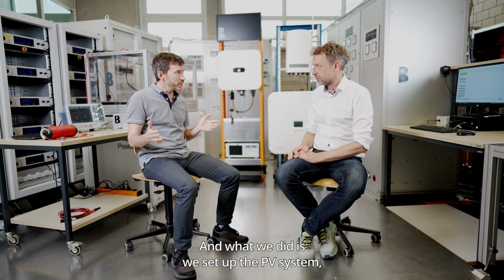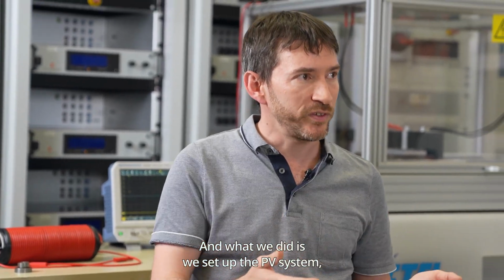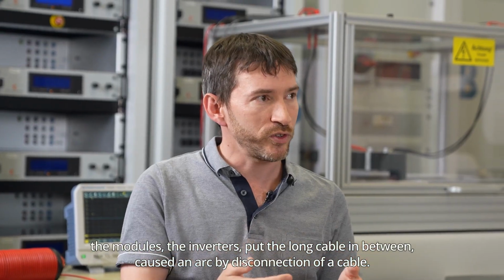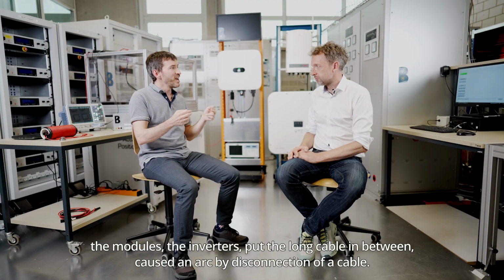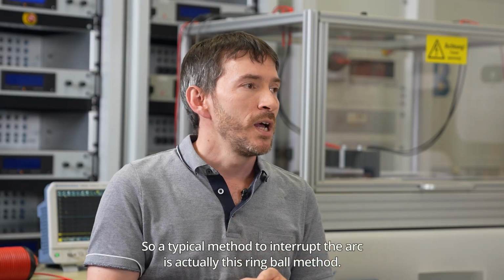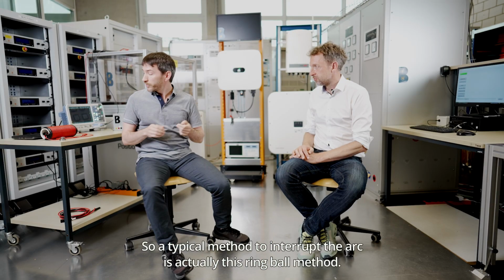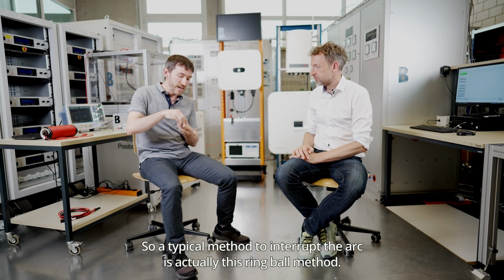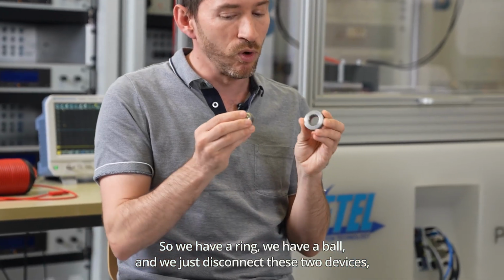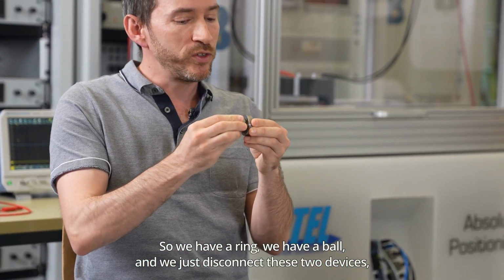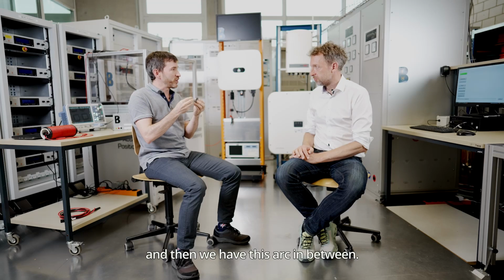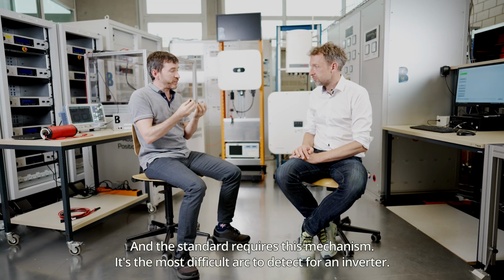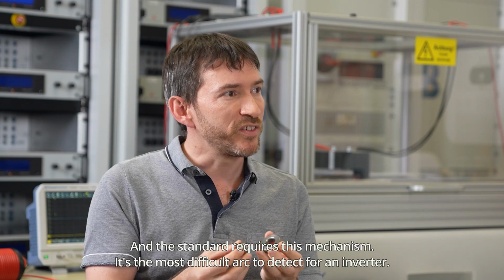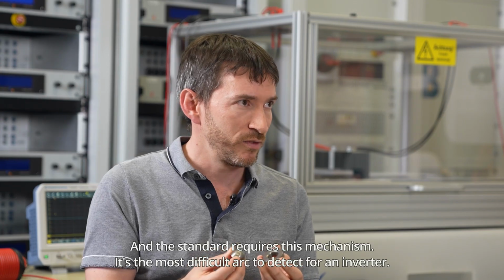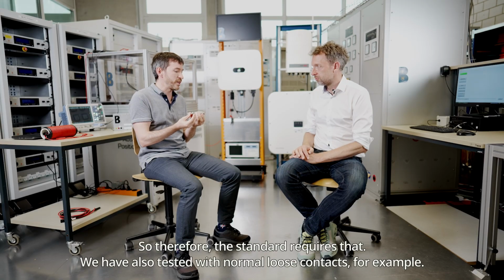And what we did is we set up the PV systems, the modules, the inverters, put a long cable in between, and caused an arc by disconnecting a cable. A typical method to interrupt the arc is the ring-ball method. We have a ring and a ball, and we just disconnect these two devices, and then we have this arc in between. The standard requires this mechanism. It's the most difficult arc for an inverter to detect, so the standard requires that.